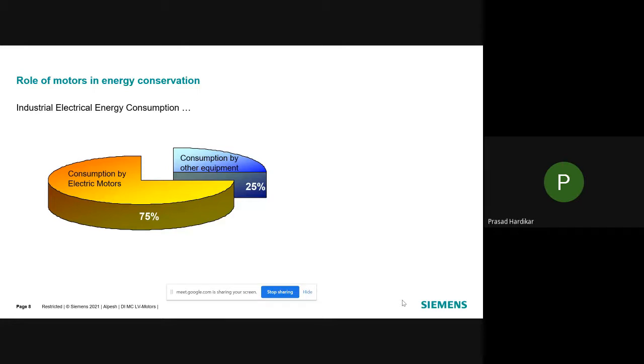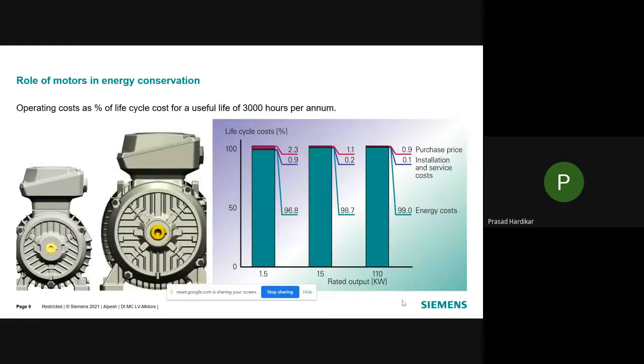Next slide, Alpesh. This is a very well-known slide, but I will repeat it. Even for a conservative figure of useful life of 3,000 hours per annum, if you look at operating cost as a percentage of total life cycle cost, which includes purchase price, installation cost, service cost, and maintenance, energy cost is a major percentage of the total life cycle cost. As you can see, for a very small rating, 1.5 kilowatt motor, the purchase price bears only a 2.3% significance in the total life cycle cost.